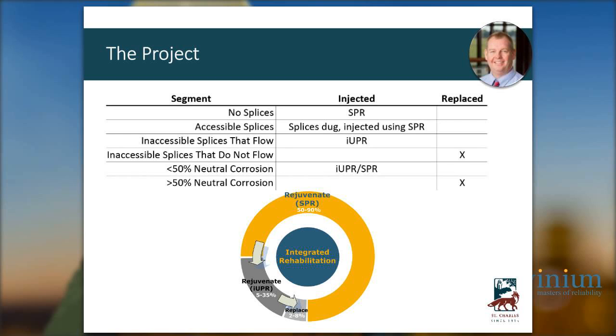If that splice will flow air, which is one of the tests Novinium does to make sure that the fluid will flow down the cable, we will go to what's called unsustained. And the only downside we see with the unsustained is that it does require a second trip. So you have a bottle reservoir under pressure at one end, and then you have a receiving bottle at the other end, but that is not a one-day process, so it ends up being a second trip, a second interruption into these people's backyards, and obviously the labor to make that second trip.